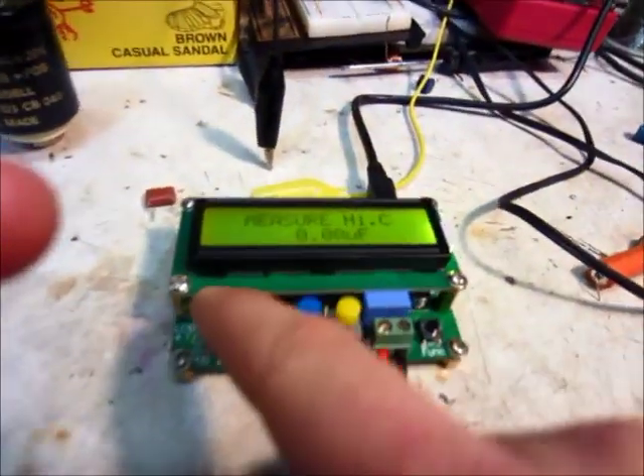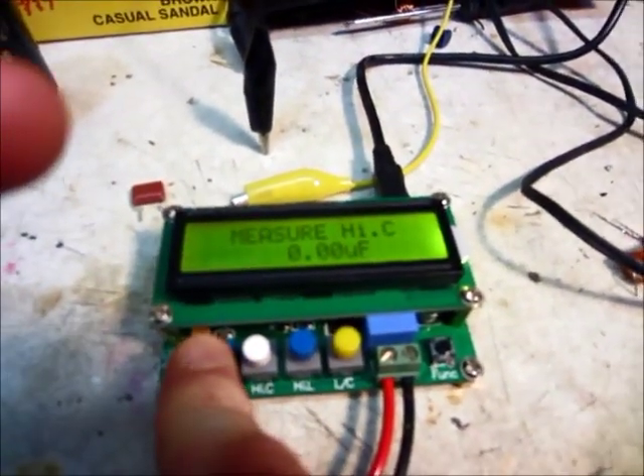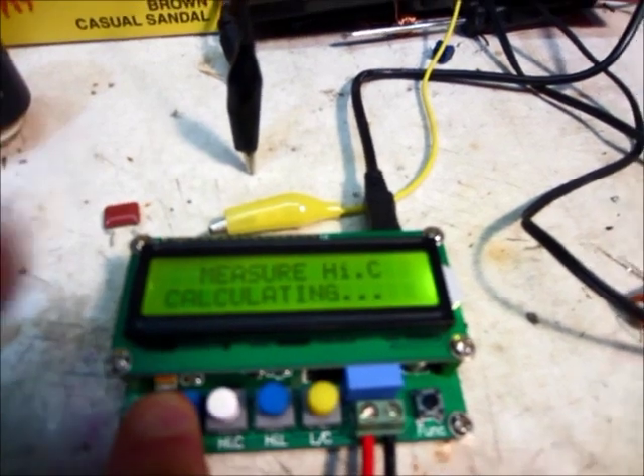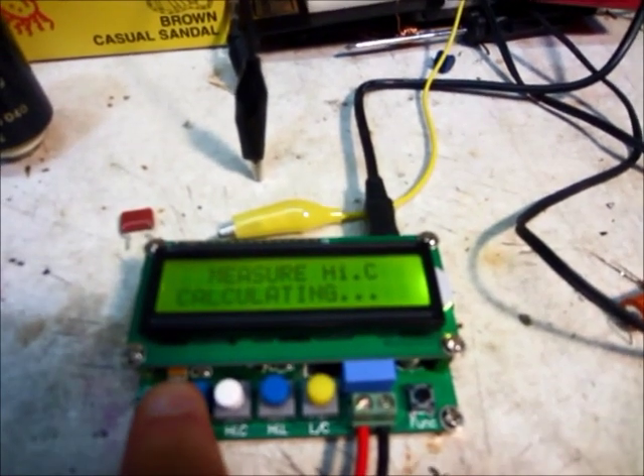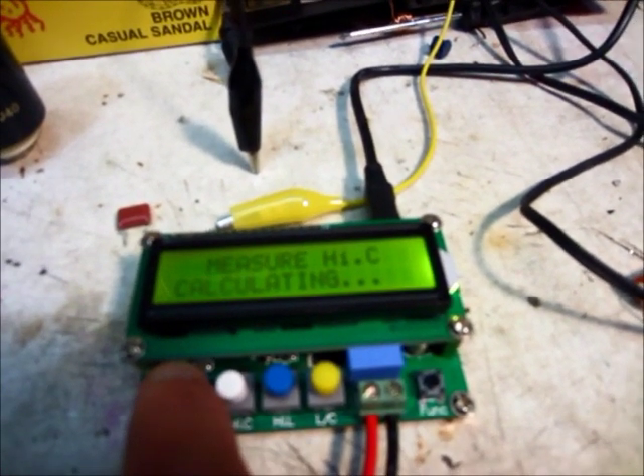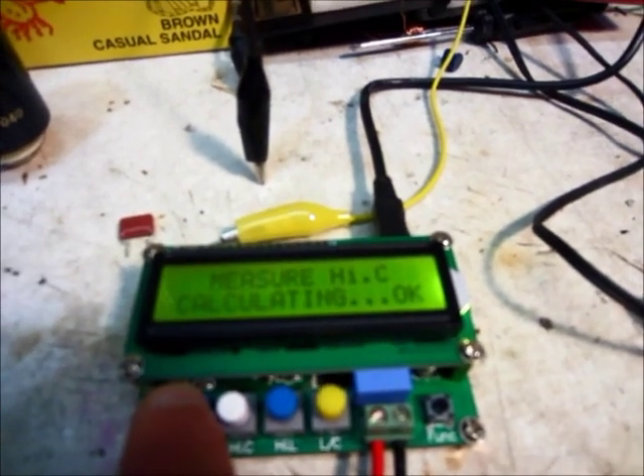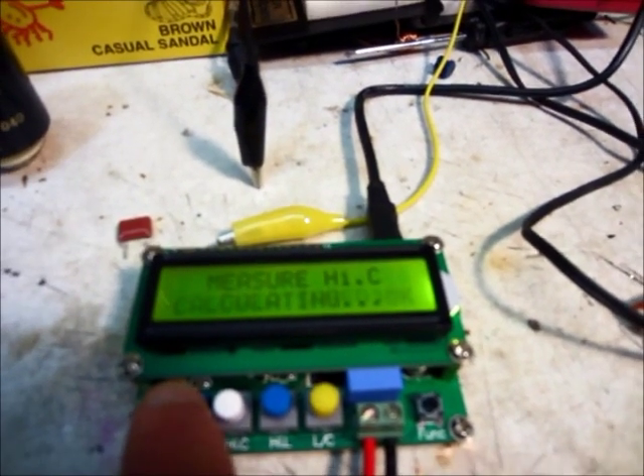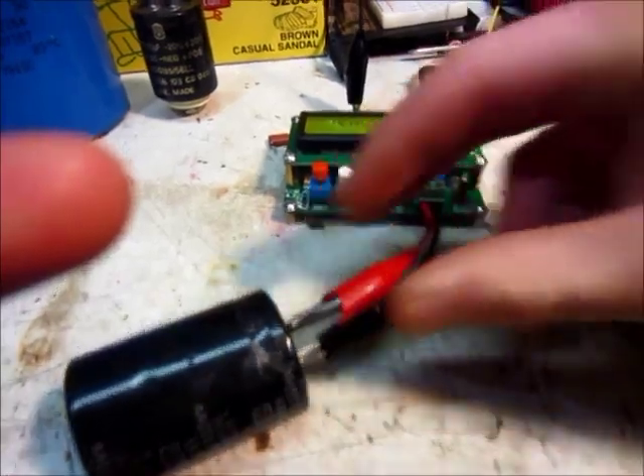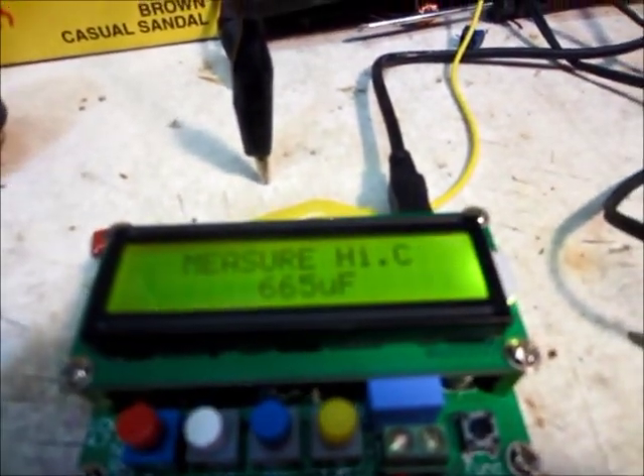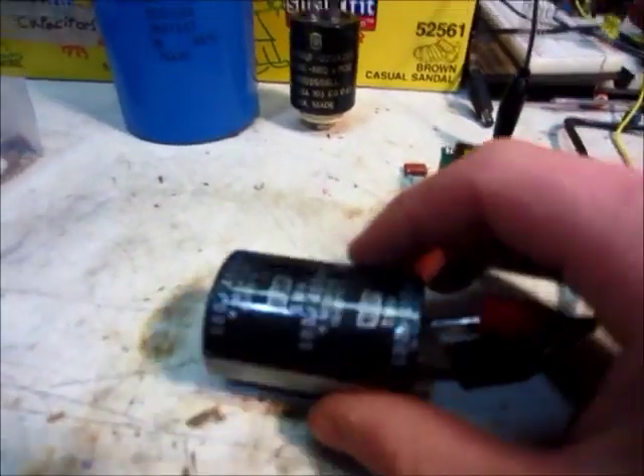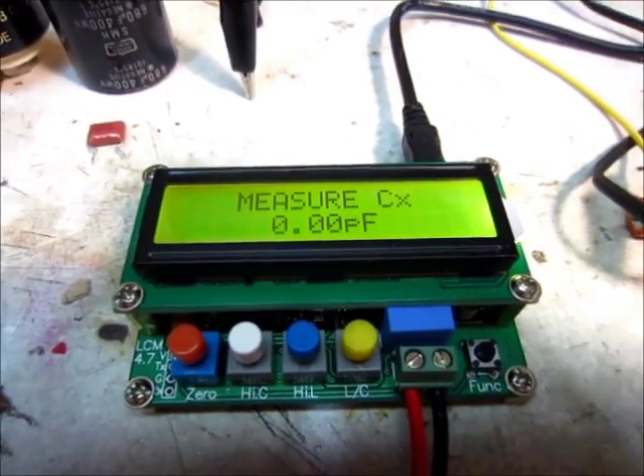It's on the high capacitance range now. You could zero it first if you want to. Hold that in. Calculating. Sometimes it takes a little bit. Okay, there we go. Data saved. Now we just clip this on here. And there we have it. 665 microfarads. That's pretty close.